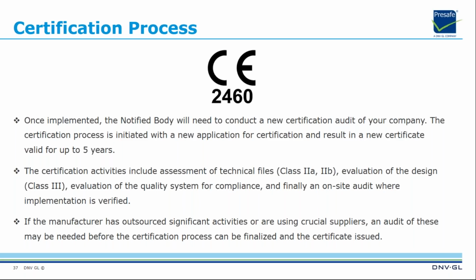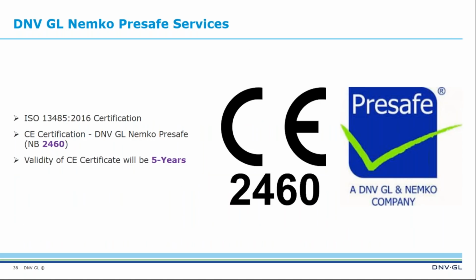The certification activities include assessment of technical file for Class IIa, IIb, evaluation of the design for class 3, evaluation of the quality system for compliance, and finally an on-site audit where implementation is verified. If the manufacturer has outsourced significant activities or is using crucial suppliers, an audit of these may be needed before the certification process can be finalized and the certificate issued. At the moment, DNV GL Nemko Presafe under notification number 2460 is ready to support you for ISO 13485-2016 certification, CE mark certification, and validity of certification for CE mark for 5 years.